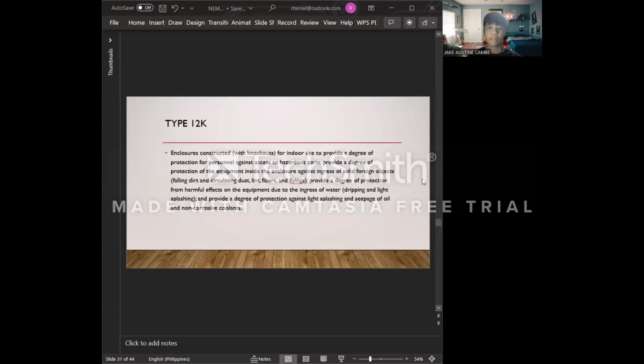Next is the type 12K NEMA enclosure. It is constructed with knockouts for indoor use to provide a degree of protection for personnel against access to hazardous parts. It provides a degree of protection of the equipment inside the enclosure against ingress of solid foreign objects.